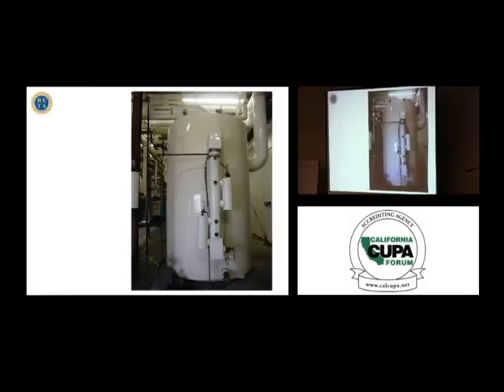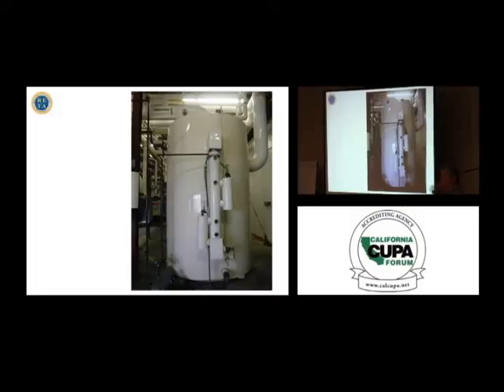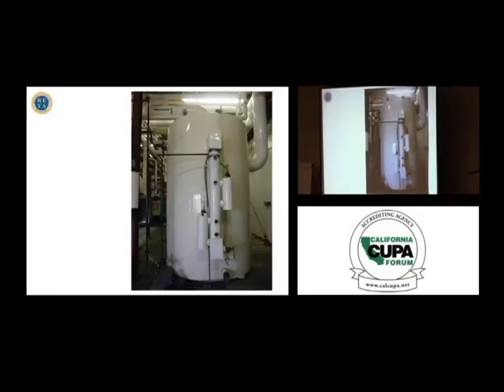Some compressors have more tolerance for liquid carryover than others. So we invest in a vessel called a suction accumulator. That's the appropriate term for this device. You go out in the field, you might hear a slop tank or a knockout drum. Well, they're talking about the function, but it's a suction accumulator. Liquid levels, what you're going to be looking at is these bullseye glasses that, when there is a liquid level there, the appearance of it is darker than one where the liquid is not. You can't tell too well in this particular illustration, but that's what you're reading for me. Sight glass 1, 2, 3, 4, and there are level switches.